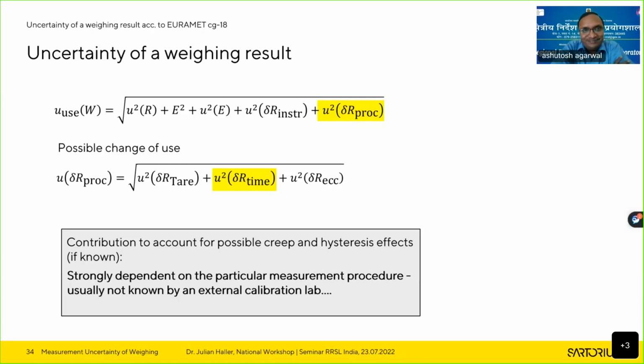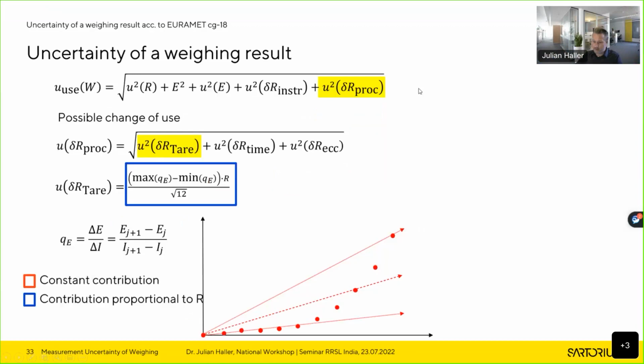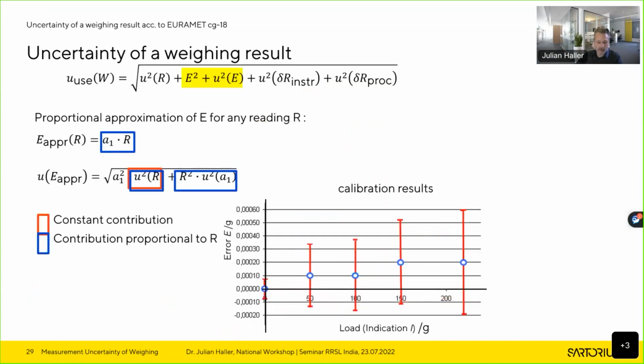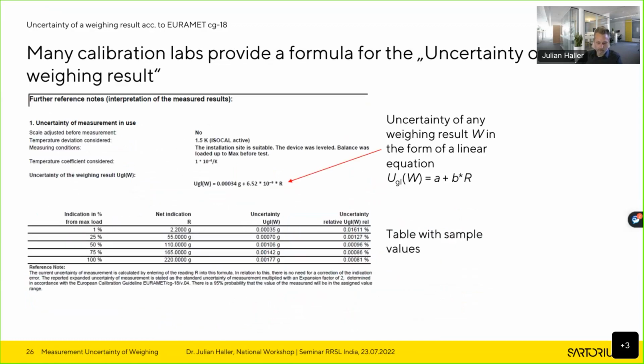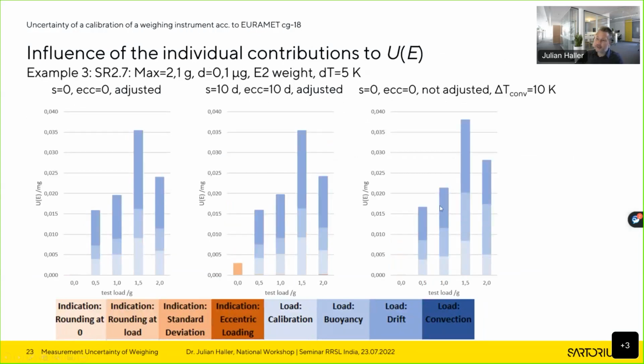From a strict formal view, you can calibrate any weighing instrument with any weight. It will just increase the uncertainty. For example, you can also calibrate an ultra micro balance with M1 weights. It's possible. It would just mean that you respectively increase the uncertainty. If you appropriately take into account the respective uncertainty of the weight class, then you can do it. That is the formal view. What I would recommend again is, if you have those respective Excel sheets that you mentioned, you can simply enter maybe an E2 weight, an F1 weight, an M1 weight, and then check, does it make a difference?